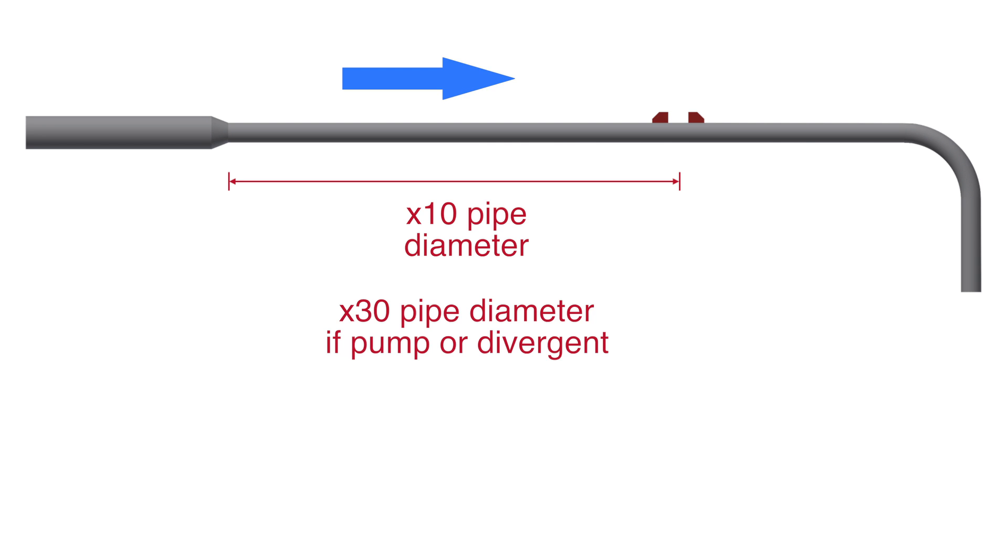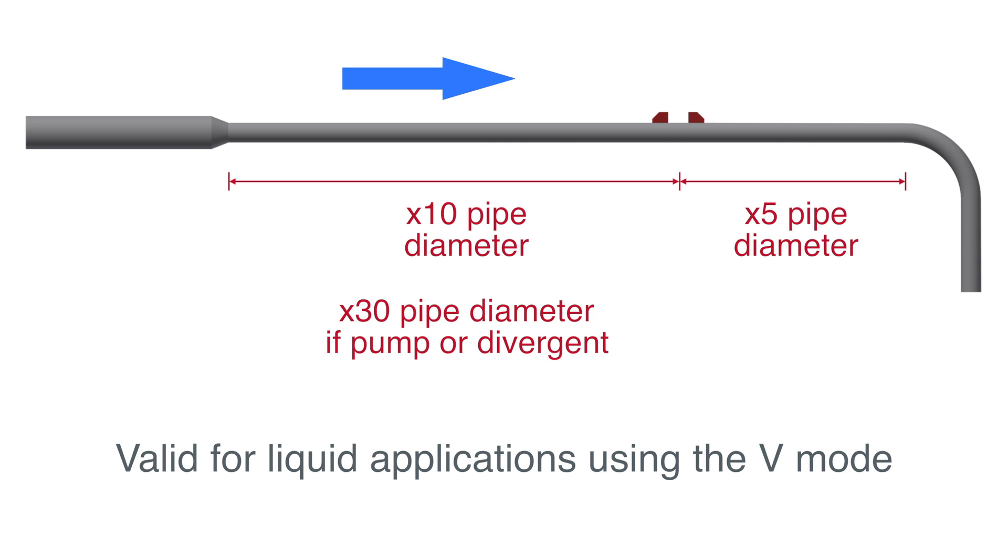Increase this distance to a minimum of 30 times the pipe diameter if the perturbation is a pump or a divergent. Make sure a minimum of 5 times the pipe diameter is available after the probes. Those values we just gave here apply for liquid applications using the V mode.